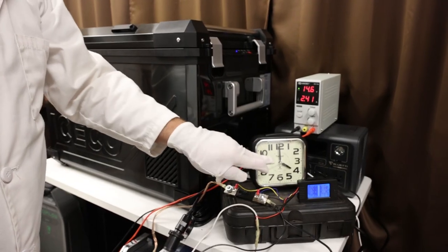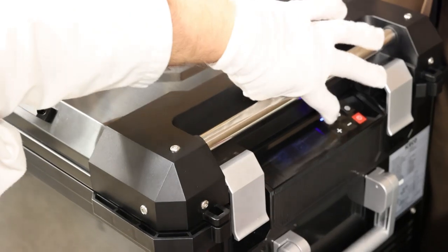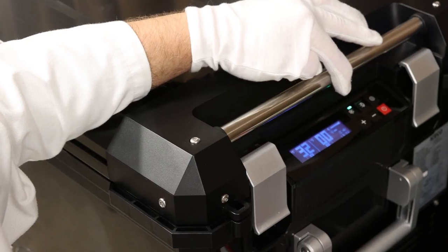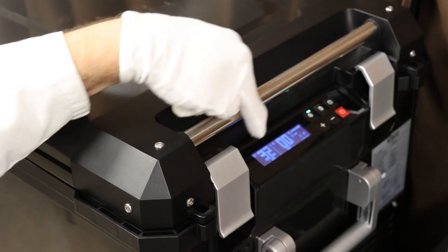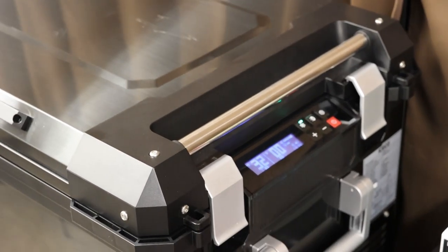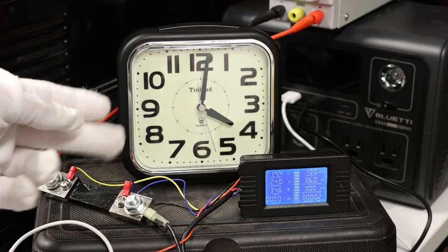A lot of times the temperature is going to vary depending on the height and where you place the thermometer. So let's go ahead and close this up. Okay, we're now going to go ahead and run this for 12 hours. I got this clock right here. This is all reset and we're going to go ahead and put this on eco mode. So switch this to eco mode by changing that from a blue to a green light just by pressing that button. So now it's in eco mode. You can see it's set to 32 and zero respectively for refrigerator and freezer. I am turning the light off to save power. So I am starting this test at 4 AM—time for me to get some sleep—and I'll come back out here at 4 PM and we'll double the number and see how much power did it use in 24 hours.